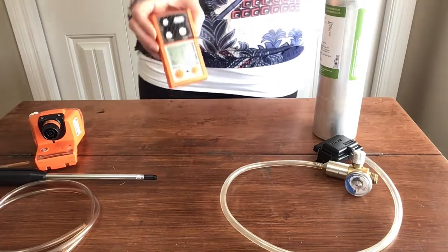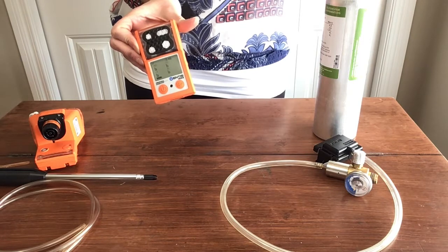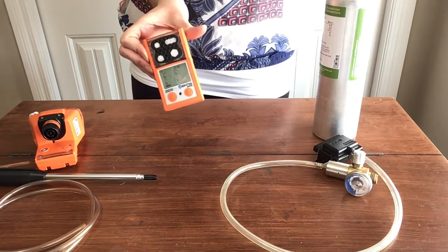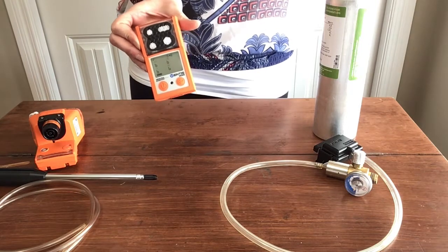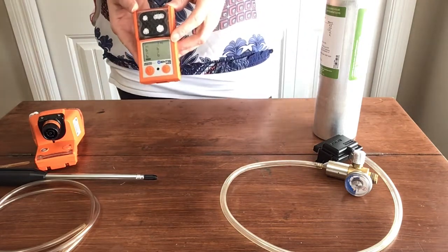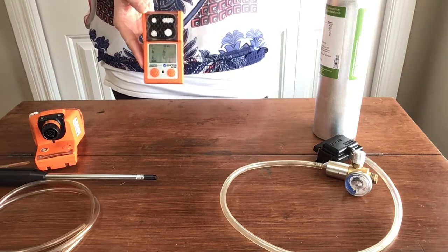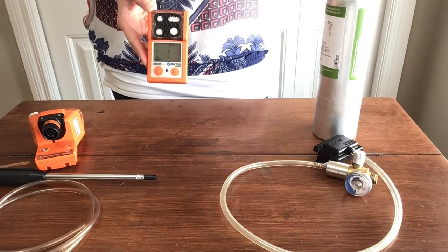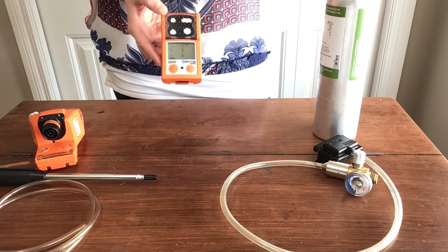These gas detectors don't have to be calibrated annually, the same way that a lot of our other industrial hygiene equipment does. The reason for that is because we're calibrating the sensors each time before we use it when we do our bump test, and we do a monthly calibration on these. When those calibrations start failing, you can try replacing the sensors because these sensors do have a lifetime or a lifespan.